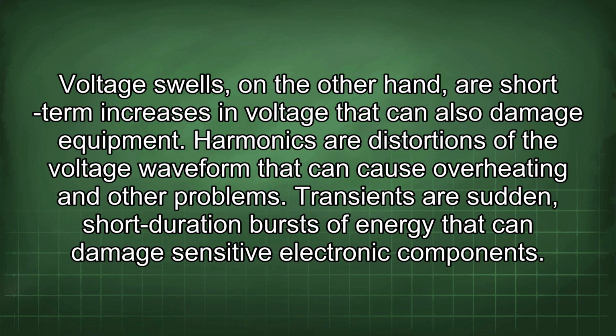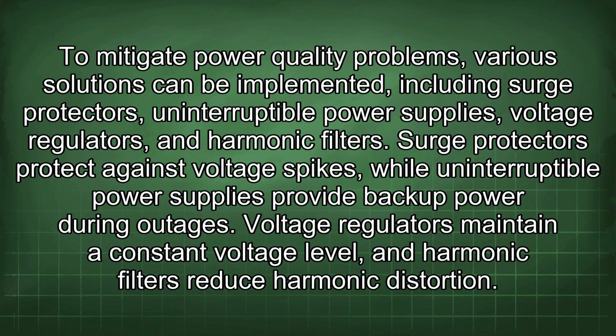Harmonics are distortions of the voltage waveform that can cause overheating and other problems. Transients are sudden, short-duration bursts of energy that can damage sensitive electronic components. To mitigate power quality problems, various solutions can be implemented, including surge protectors, uninterruptible power supplies, voltage regulators, and harmonic filters. Surge protectors protect against voltage spikes, while uninterruptible power supplies provide backup power during outages. Voltage regulators maintain a constant voltage level, and harmonic filters reduce harmonic distortion.